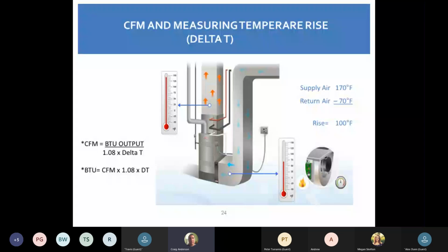High stage is usually between 40 and 70. Mid-range is great. We always want to stay away from the high end or the low end. If you're too low, then the people are getting cool air out of their register instead of lukewarm or hot. But always do your temperature rise, set your fan speed to what is needed. This is going to tell you if you have a bad filter. It's going to tell you if you have bad ductwork or a dirty coil.